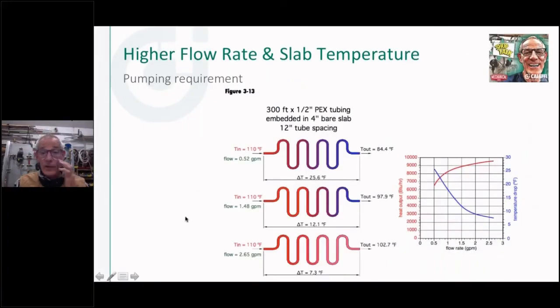Yeah. All right. So here it is on a slab. And so what's interesting about this is, let's call this what we modeled here is a 300-foot loop of 1/2-inch PEX tubing in a 4-inch bare slab, 12-inch on center. And what I'm going to do in all these instances here is I'm going to give them the exact same supply temperature. I'm going to keep that temperature consistent, and I'm going to change the flow rate. And look what that does to the delta T going across here. So on this one here, we're running this at a 25-degree delta T, so 110 coming out at 84.